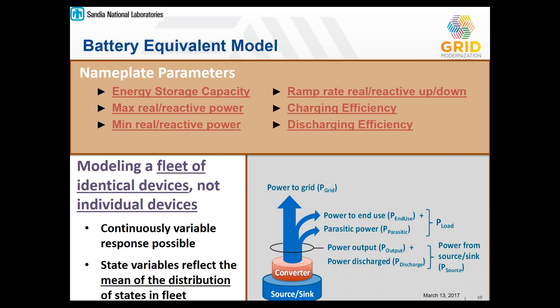Just one more slide on the battery equivalent model. It has nameplate style parameters, things like capacity, maximum power, minimum power, ramp rate, charging efficiency, and discharging efficiency, and these are abstracted quantities for how the system is represented. And again, this is modeling a fleet of identical devices, not an individual device. So this is not us sitting down and trying to model a refrigerator that is turning on or turning off. This is meant to be modeling 1,000 refrigerators, 10,000 refrigerators that are being coordinated using smart communications to really provide these services in bulk.